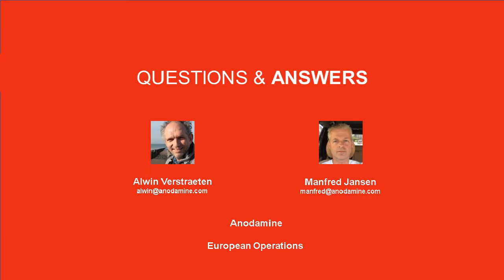Well, that's very simple. As I showed very extensively, these systems with copper inside are probably run on reducing conditions, so with oxygen scavengers to avoid the existence of oxygen, which could react with the copper alloys to make copper salts out of it. We have many of these kinds of systems, about 30,000-35,000 megawatts of generated power running with anodamine. So that's really common knowledge for us.